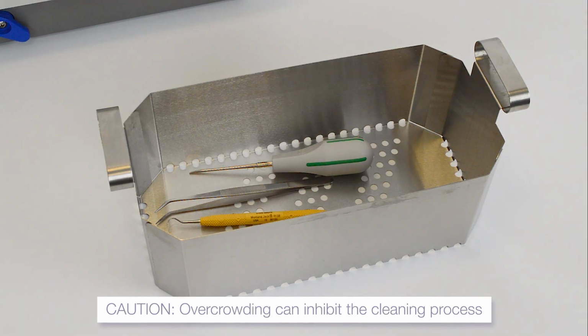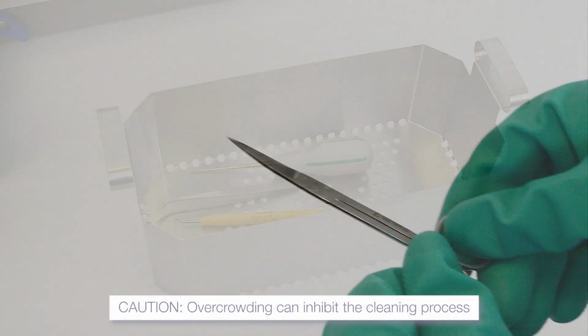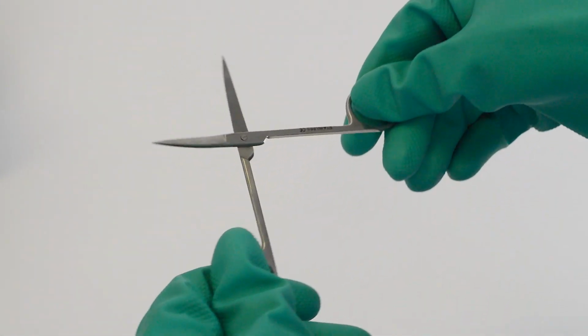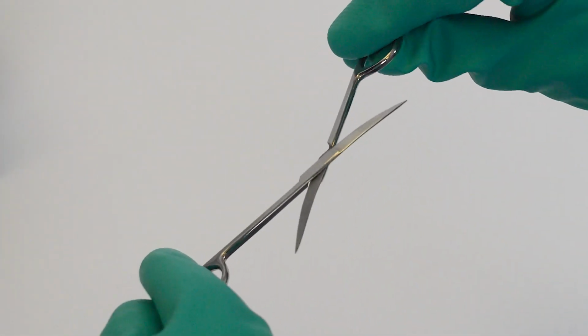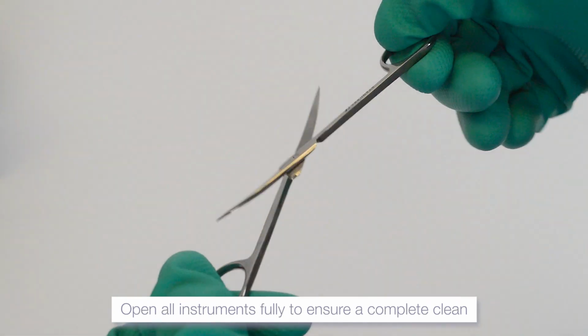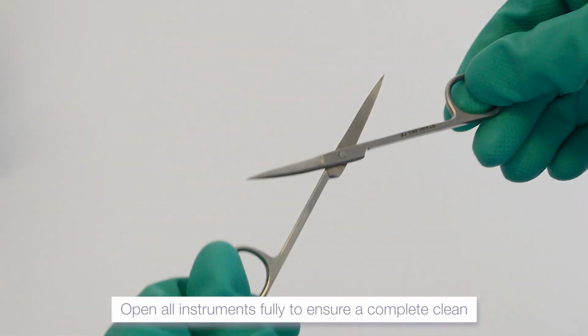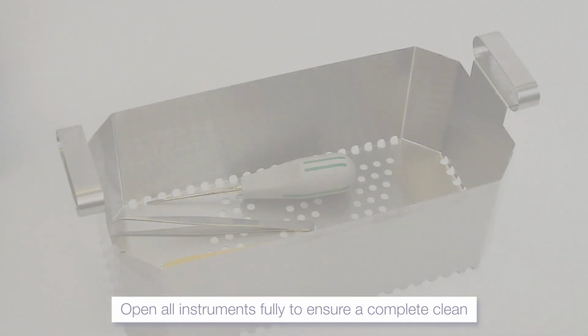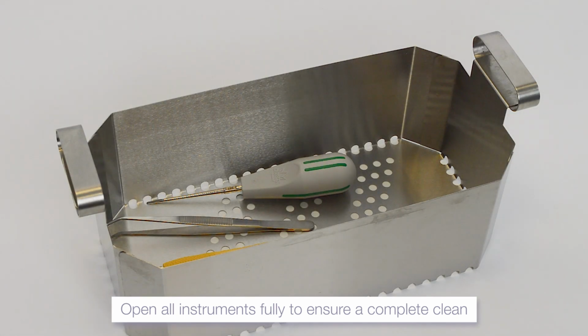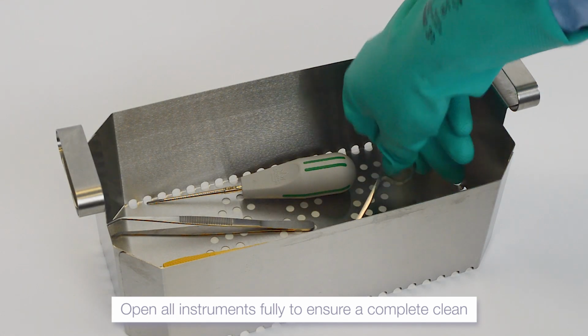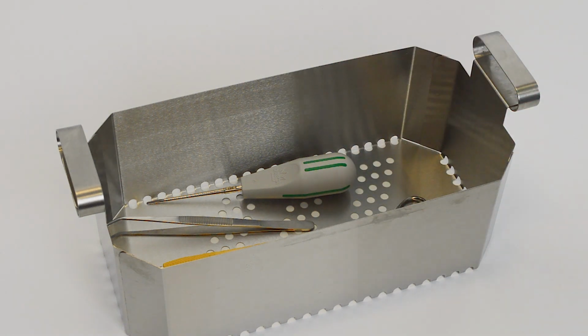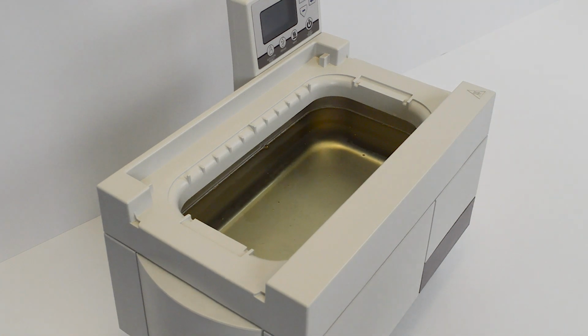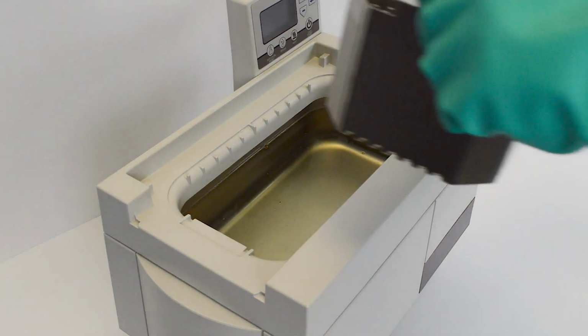Used instruments should be fully opened before being placed carefully inside the ultrasonic bath and immersed in the ULTRAbio solution. Careful attention should be paid to ensure air can escape from hollow objects. Be careful not to overcrowd the ultrasonic bath with too many instruments. Ensure instruments are fully submerged but not touching each other, as this may inhibit cleaning performance.